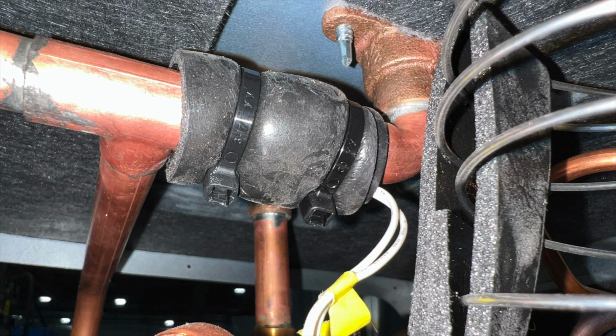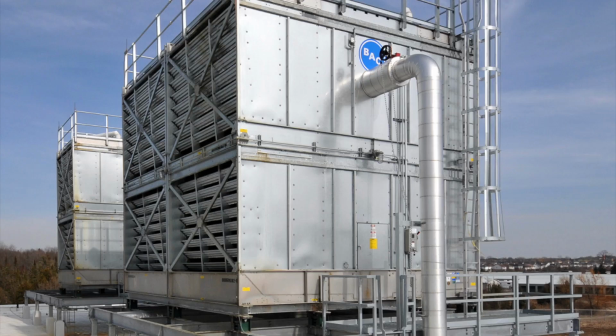This flash code can occur as well if the temperature of the leaving water drops below 55 Fahrenheit. It will reset when it goes above 60 Fahrenheit. Check with the building's maintenance personnel to make sure the cooling tower is working properly. Temperature is within parameters and flow rates are correct.